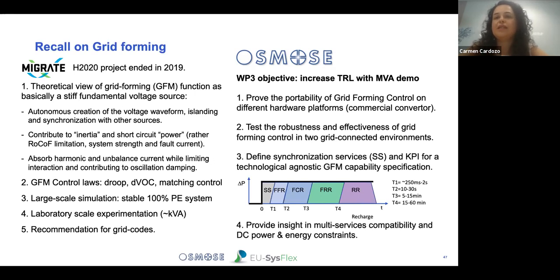This is an illustration: we have classical reserves like frequency containment reserve, and now also fast frequency response. What we understand by synchronization services is everything below that, which relates to bringing back this grid forming capability. Grid following, current-controlled classical converters can provide fast frequency response, but maybe not synchronization services. So the idea is, knowing this conceptually, to define it and provide insight into how one device can provide these multi-services.